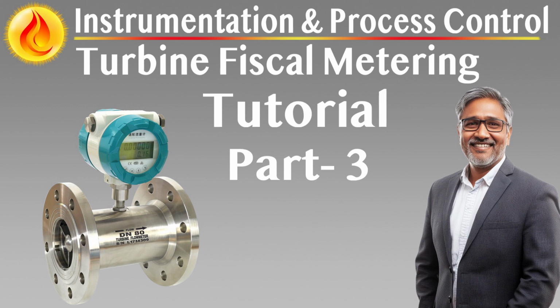Vane failure detection and redundancy. Each turbine meter must be equipped with mechanical or electronic means of detecting rotor or vane failure. This function must operate independently of the primary pulse train and generate a diagnostic alarm if abnormal rotational behavior is observed. Detection mechanisms must be sensitive to conditions such as jamming, disintegration, or fluid-induced overspeed, providing early warning before flow measurement becomes unreliable.